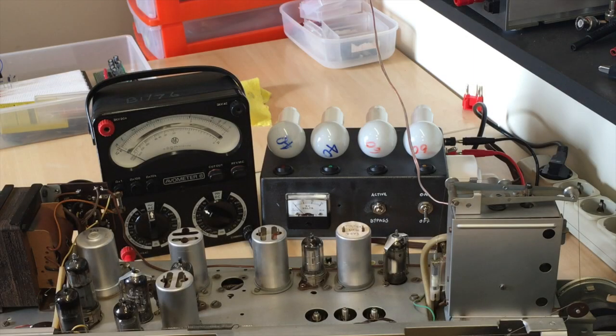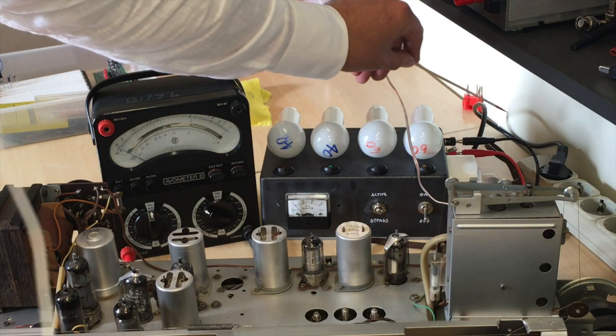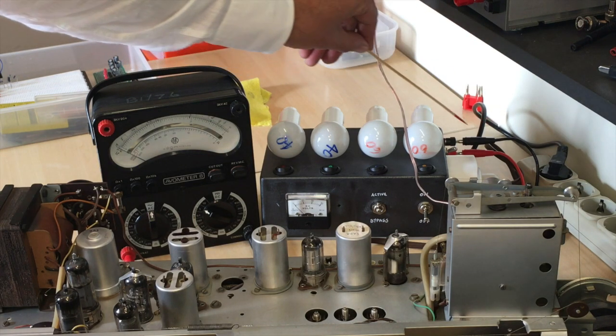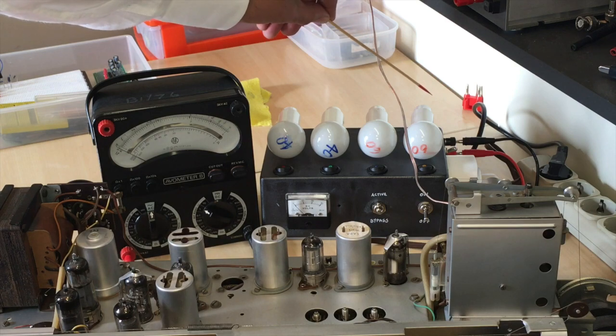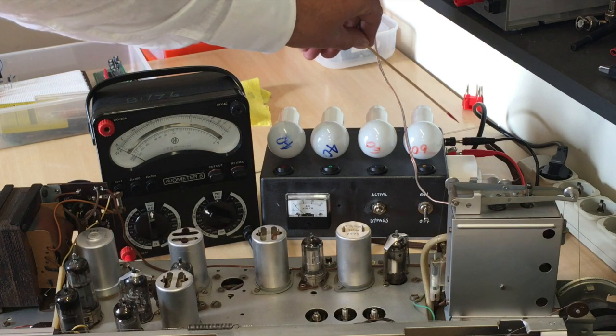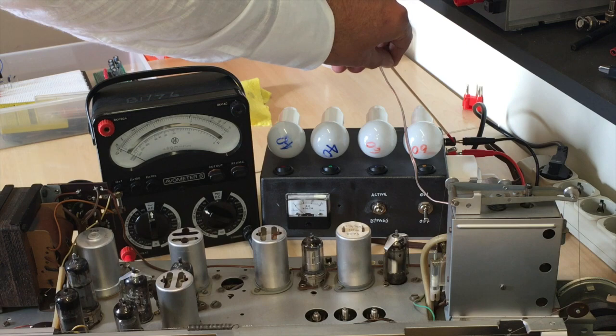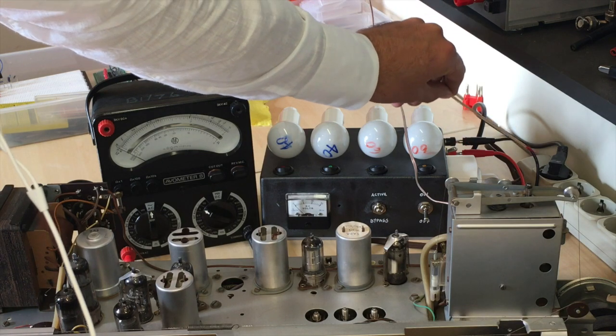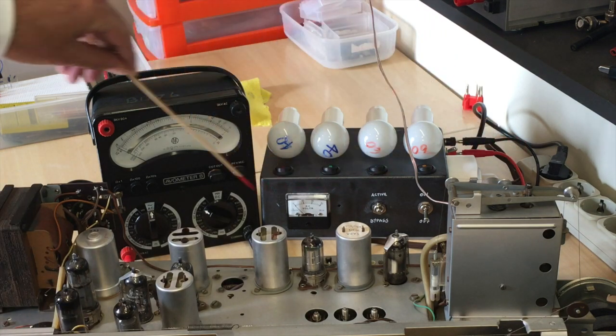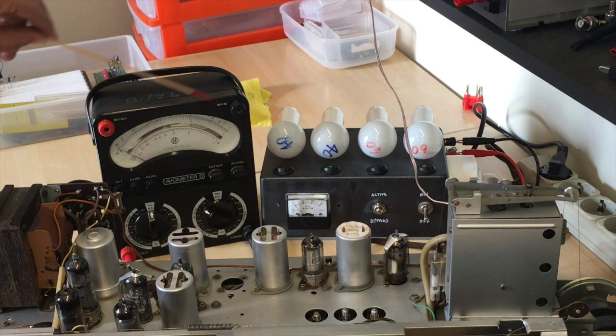The way this light limiter works is as follows. I have mains coming in over here into the light limiter. It then goes through a metering output. These two connectors here go to an ammeter over here. That can be bypassed if I don't want to check the current.